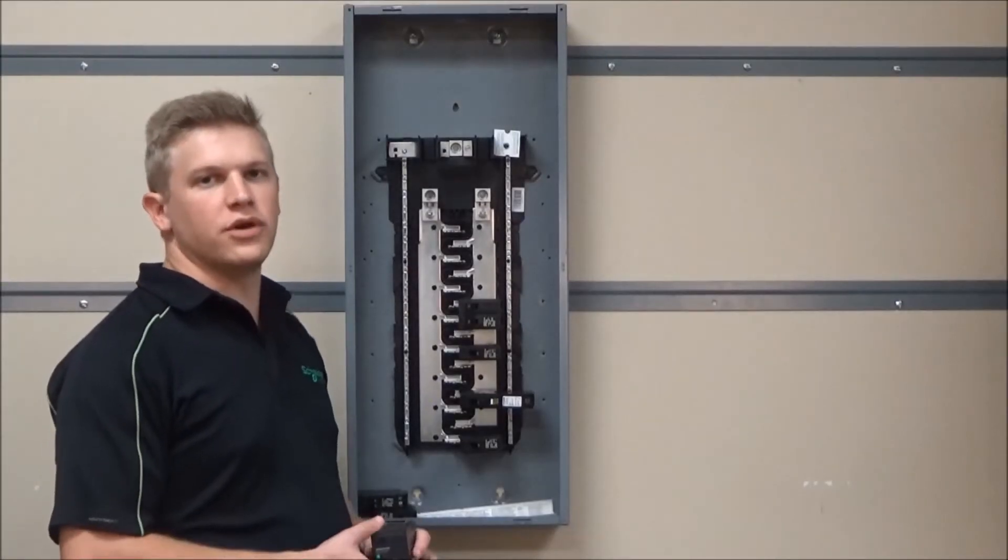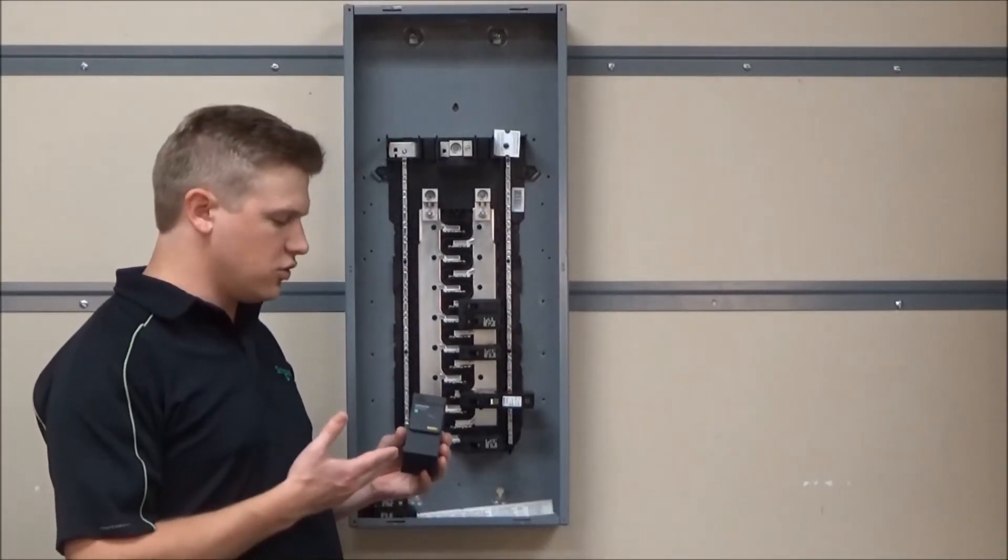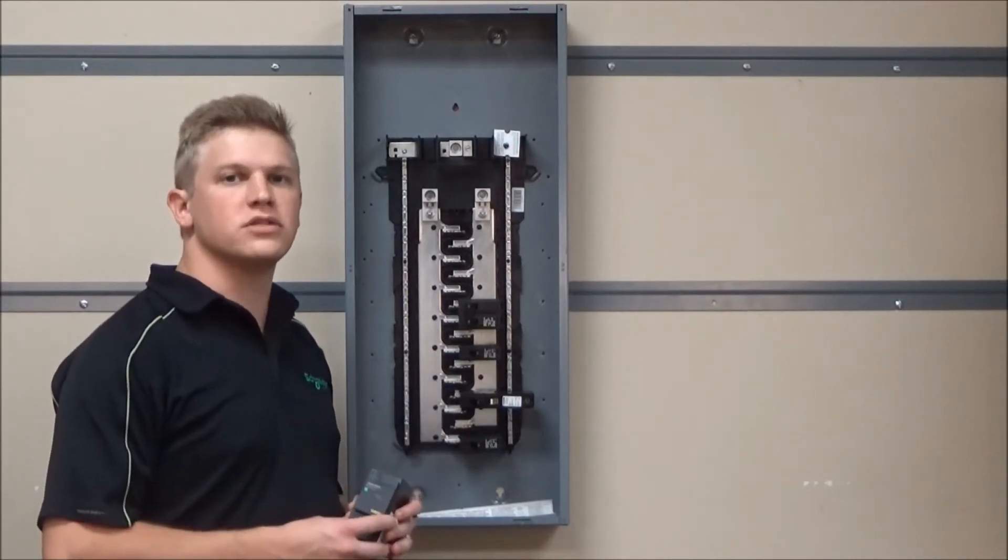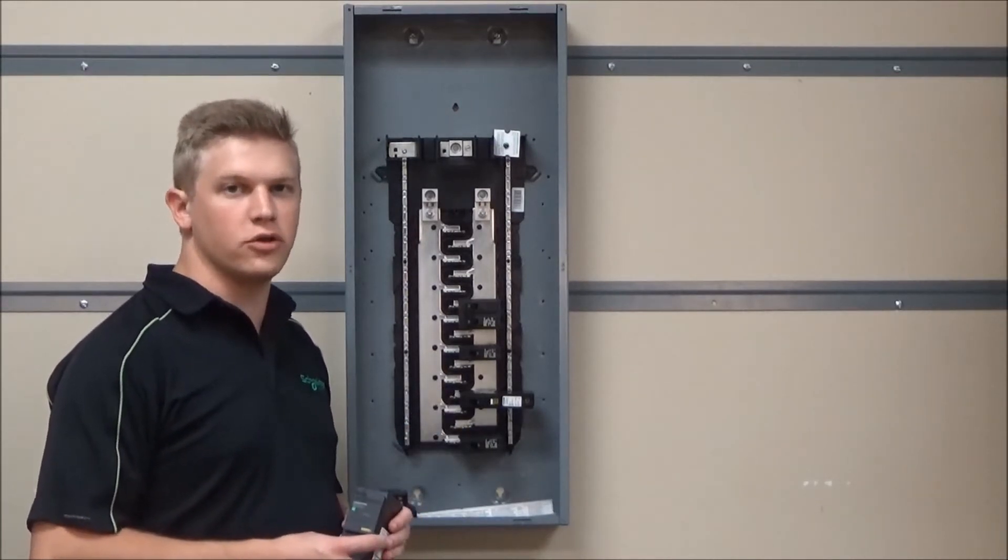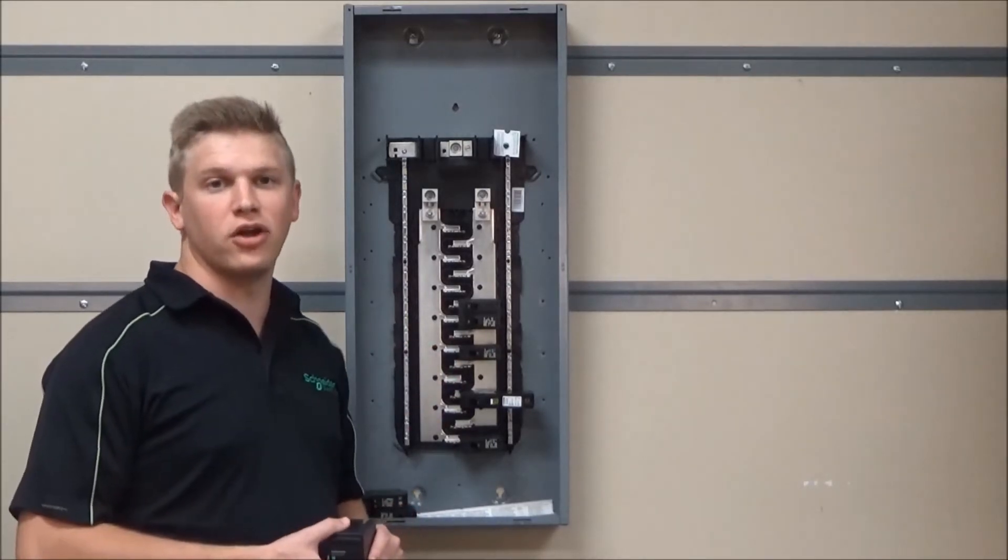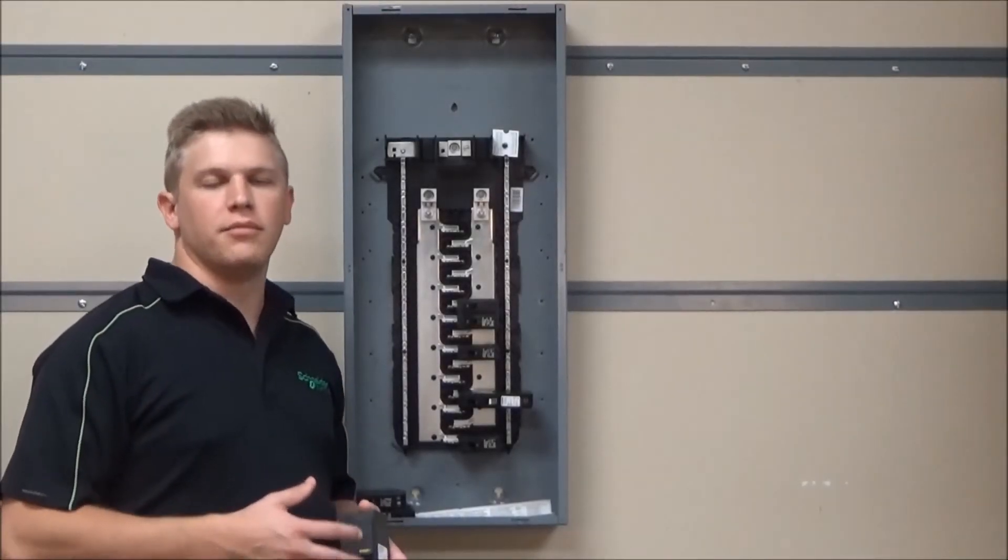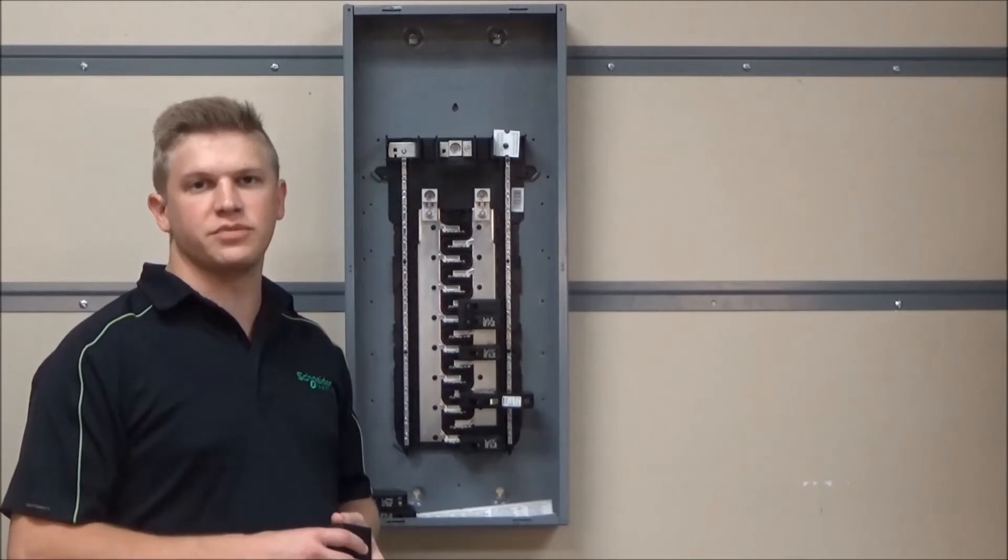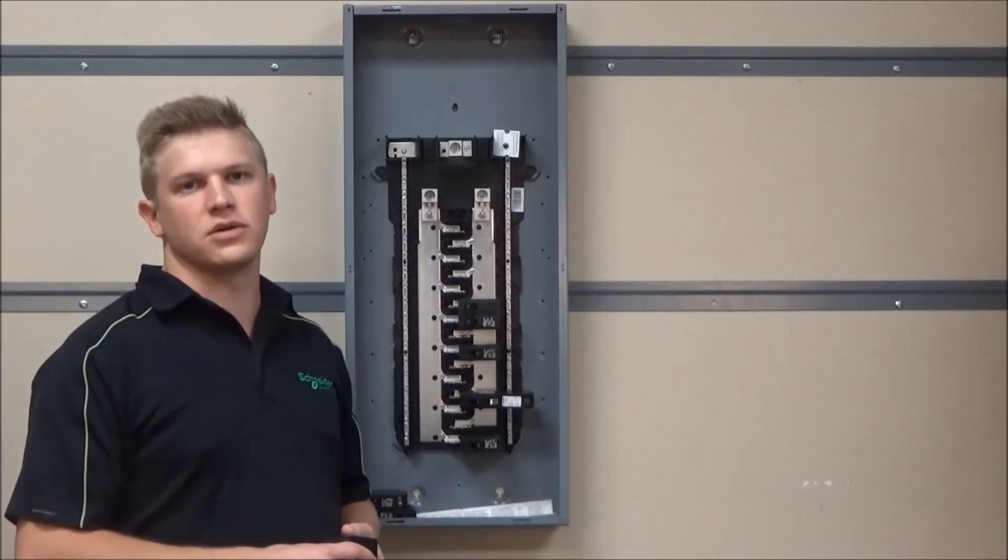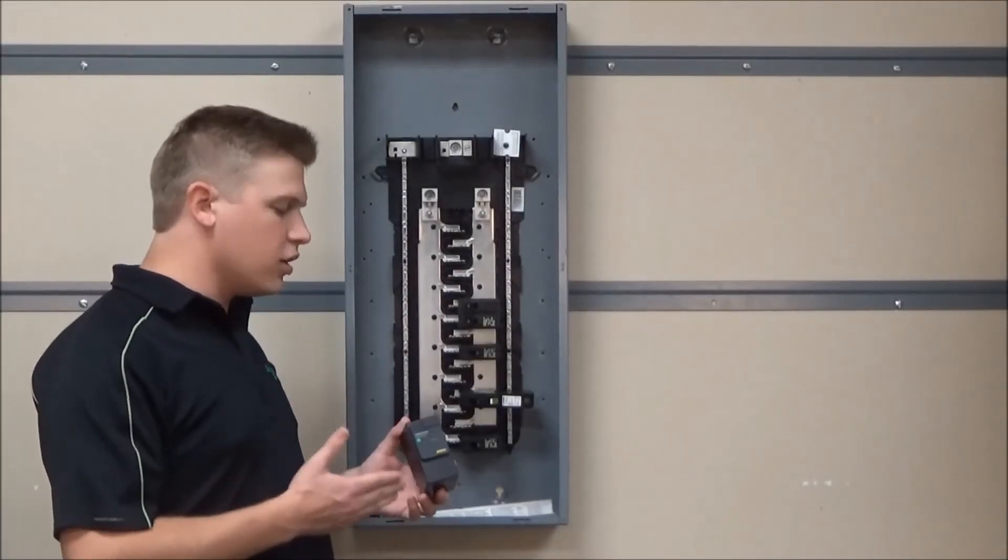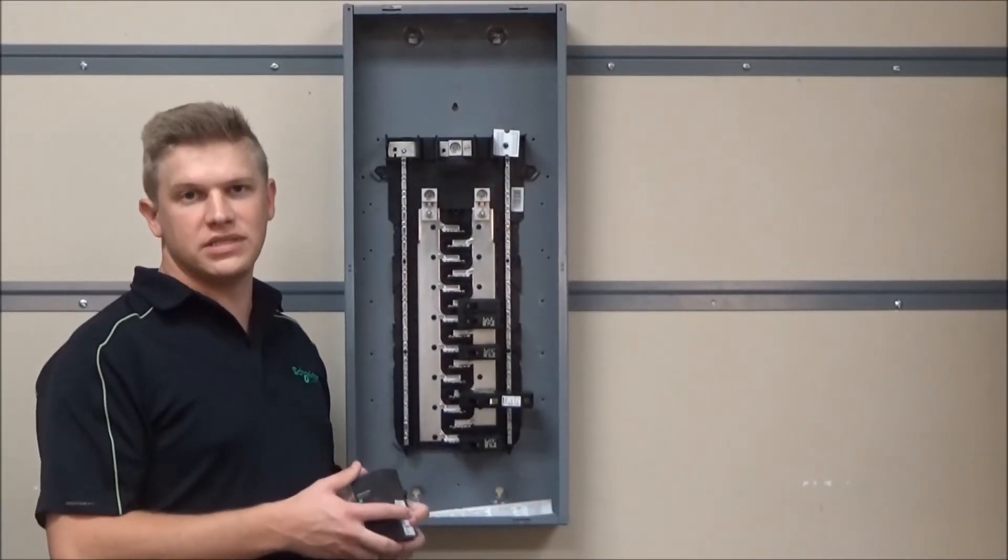In this video, we'll be showing you how to install the HOM 250 PSPD whole house surge protective plug-on neutral surge breaker into a Homeline plug-on neutral panel. Before installation, make sure to always consult the safety information in the instructions provided with the device and never work on energized equipment. For the plug-on neutral version, there is no pigtail to attach to the neutral bar.